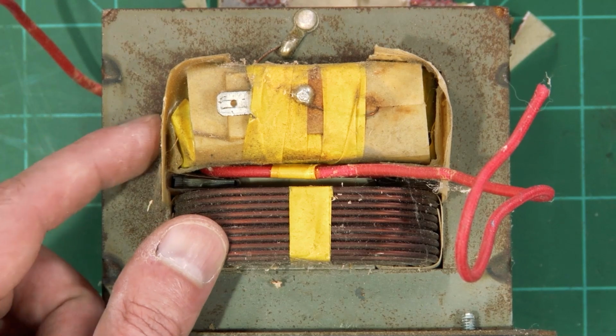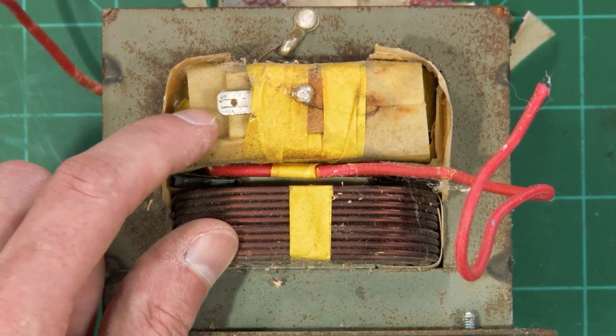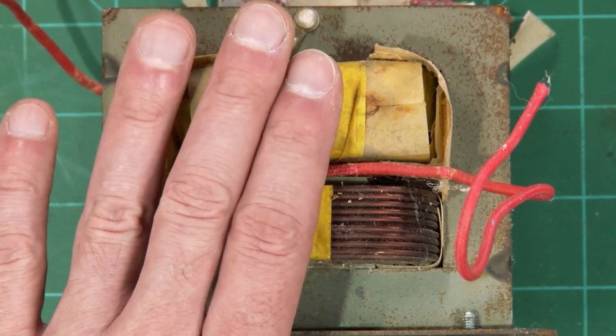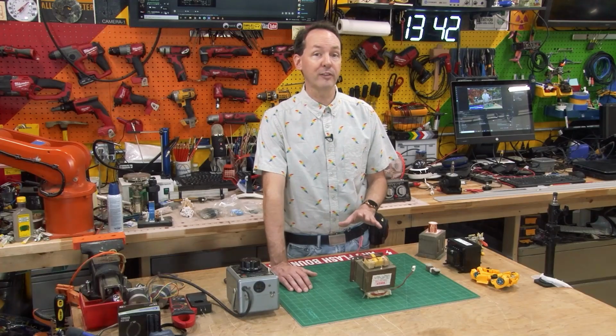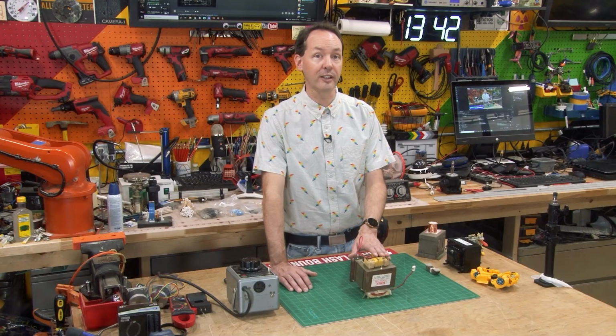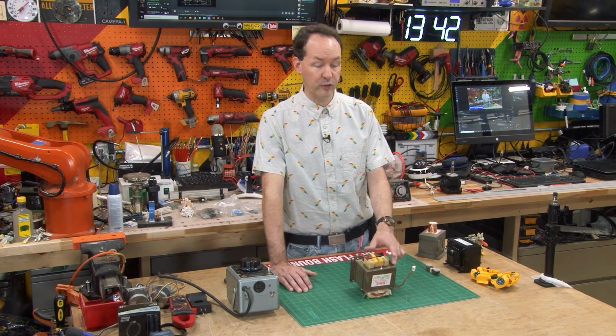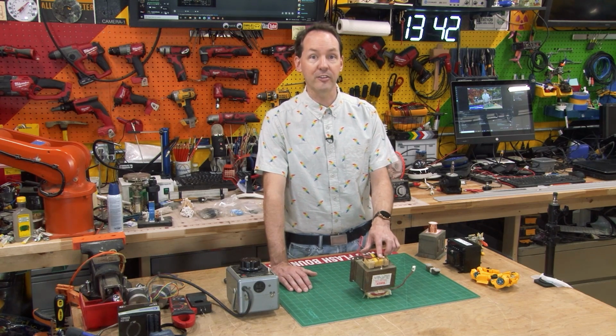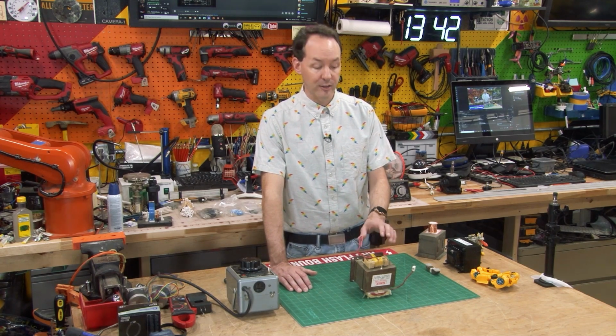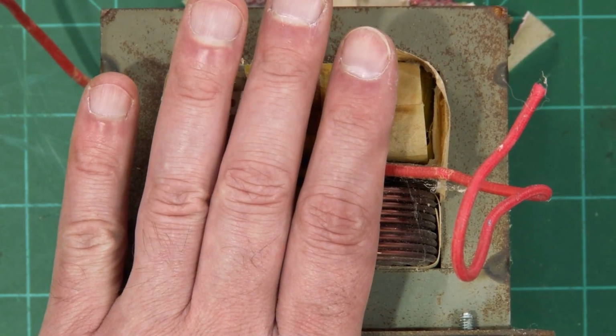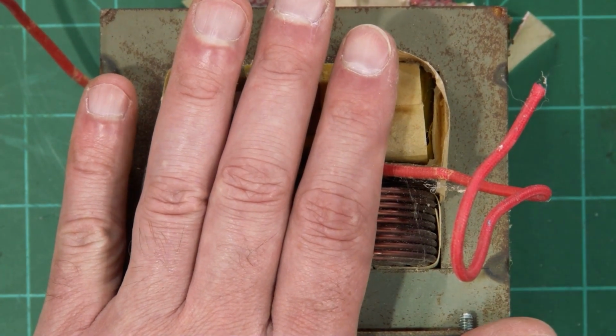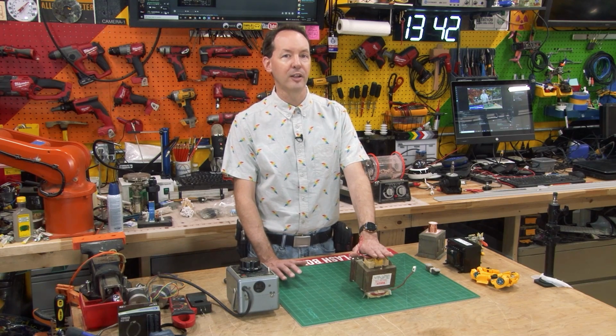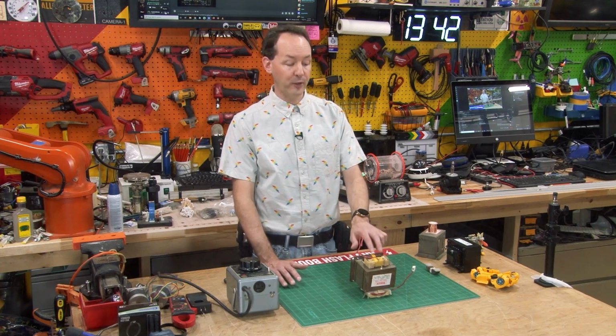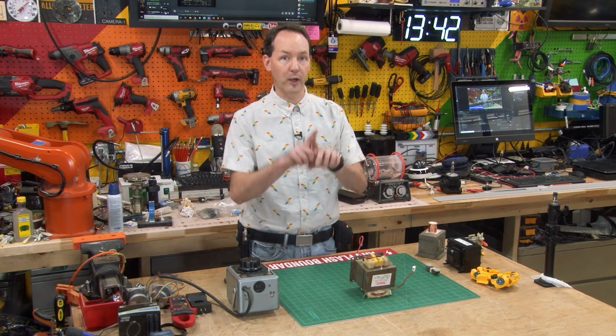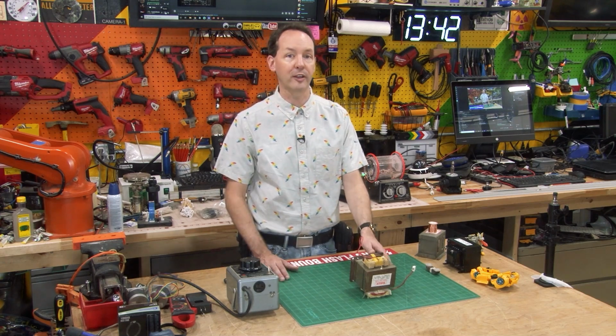The next winding we come across up top here, this is the secondary winding. This is where we get the high voltage out. On microwave oven transformers, it's usually grounded at one end to the core, and the other end is a single high voltage terminal. Some high voltage transformers like MOTs — it's rare with MOTs — but sometimes you'll get one where both ends of the high voltage are brought out to wires, but usually one's grounded to the case.